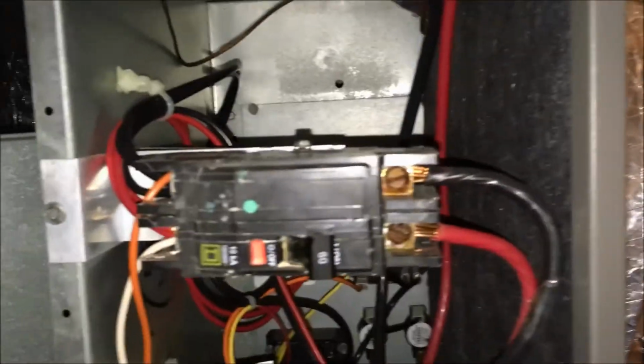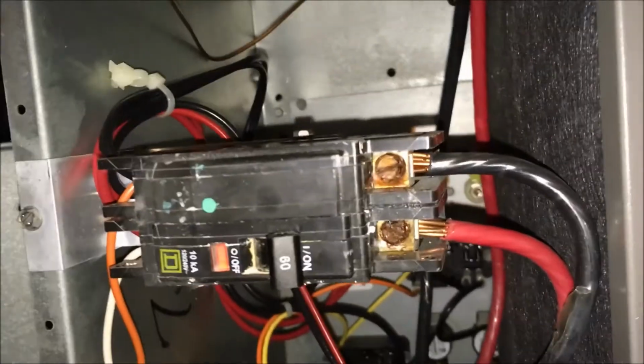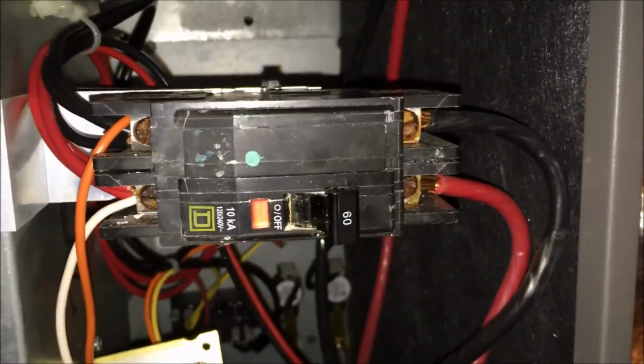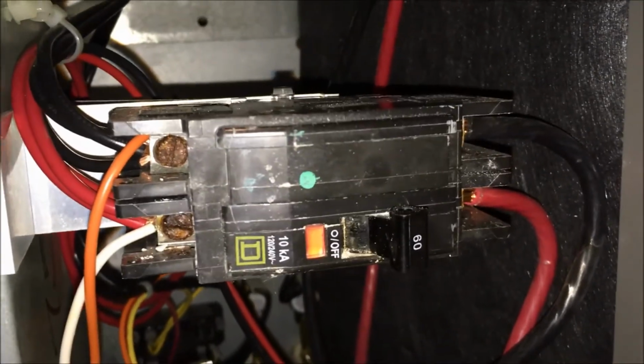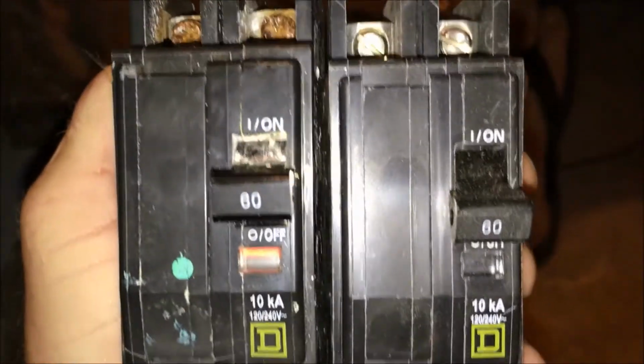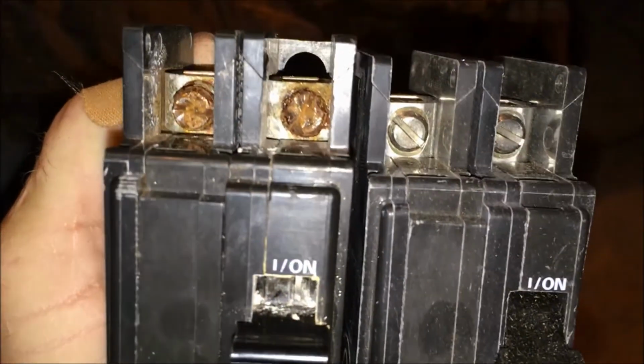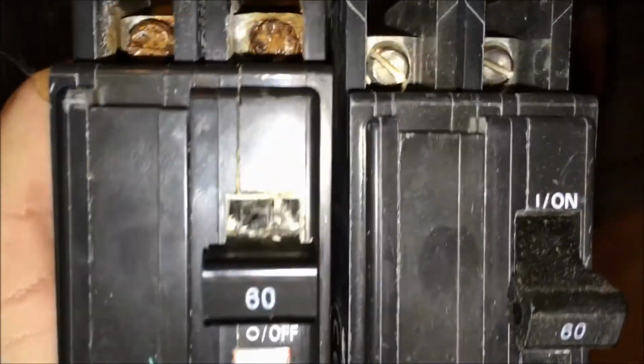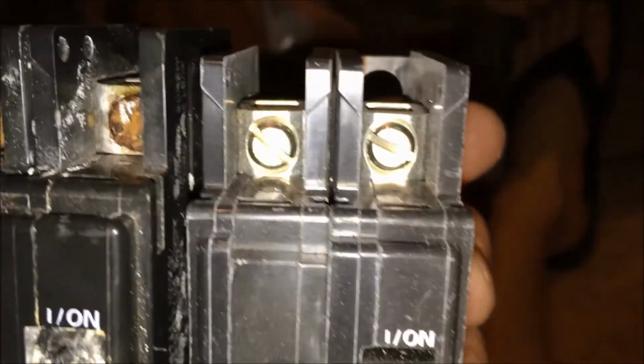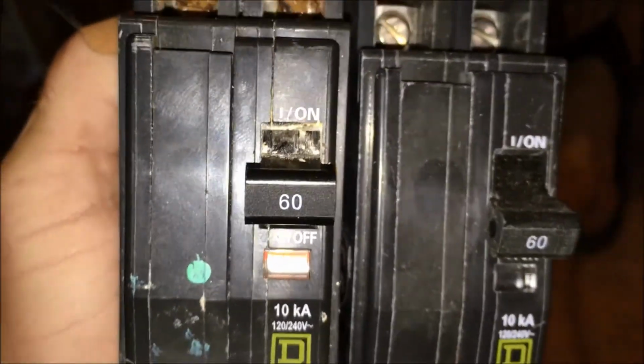Making sure I'm safe, I'm measuring the AC voltage across this to make sure I don't have any voltage when I'm taking this apart. I don't want to be shot out the side of my house. Here you see the condition of the old breaker on the left. I don't know where all that moisture came from that caused all this corrosion, and the new breaker. So I'm going to replace that now. And this should resolve the problem. The breaker did not have continuity when the switch was turned to the on position when I was testing with a multimeter.